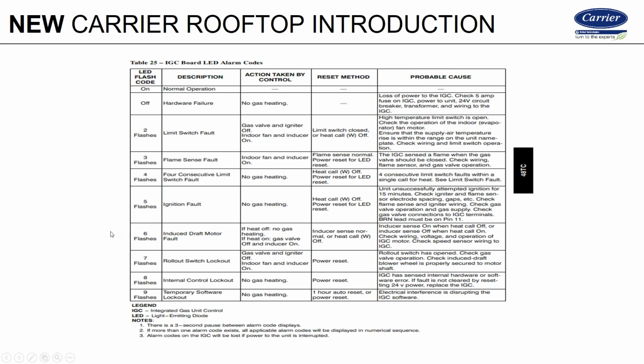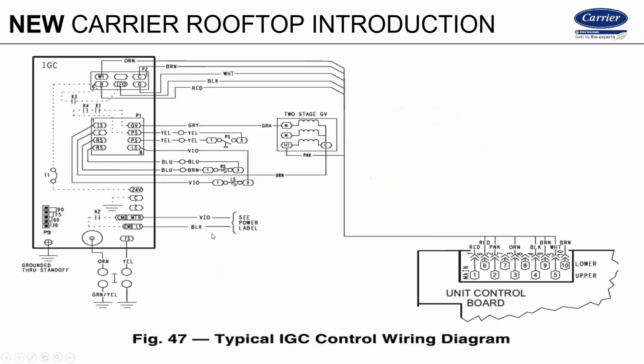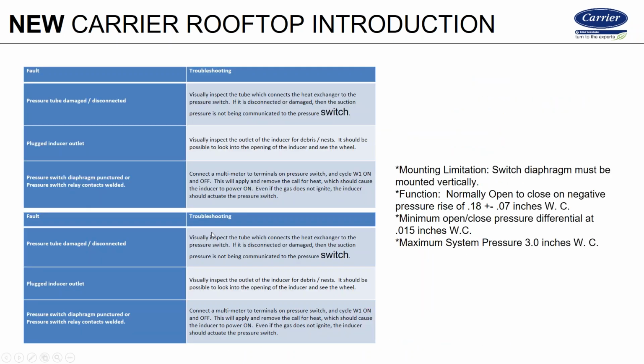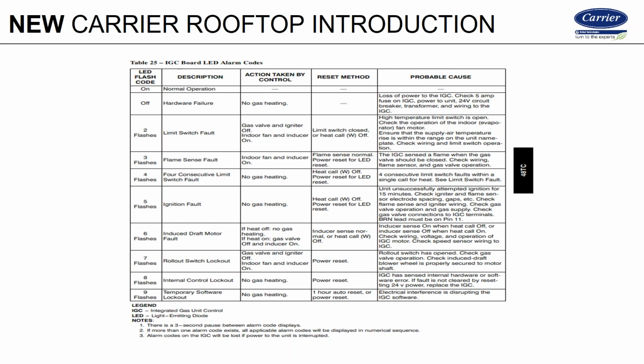The next one is 6. 6 flashes means we didn't prove that the inducer was running, which would be that pressure switch. So you got the pressure switch troubleshooting here, which is in the book, okay? 7, rollout. So if we got a flame rollout from whatever the case may be, burner alignment, air in the gas, which is giving us goofy, kind of funky flame characteristics. If we got prevailing winds blowing into the exhaust, any of those things can cause flame rollout, as well as a compromised heat exchanger or something with the induced draft wheel. But typically you usually get a fault code 6 along with that or before it.